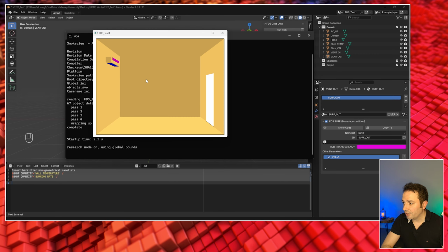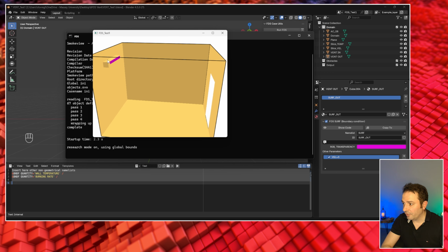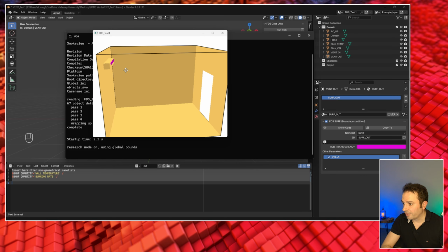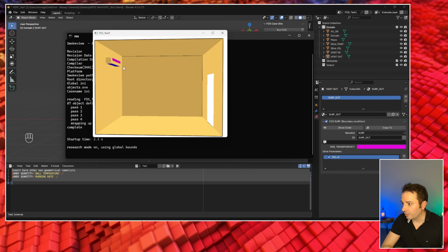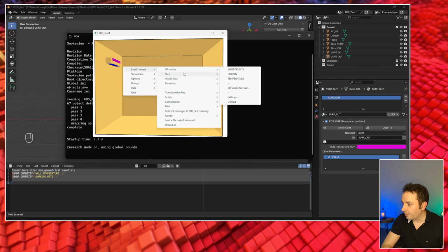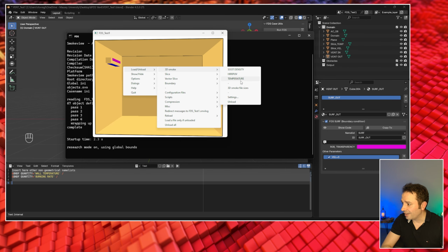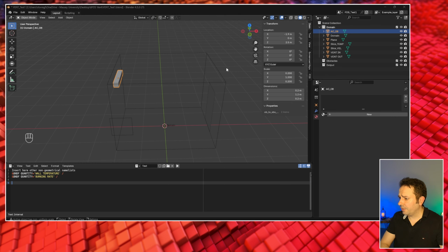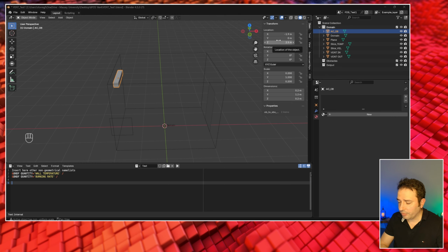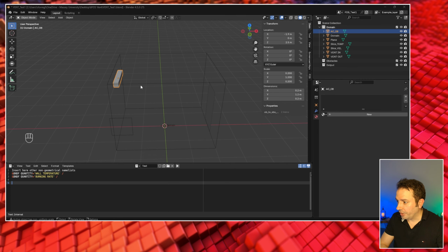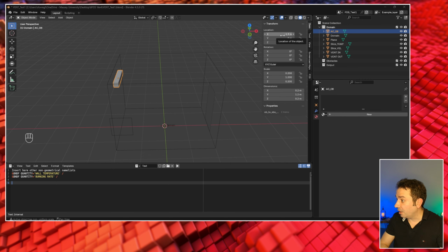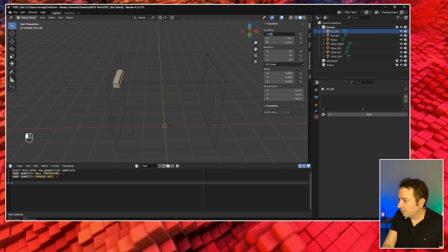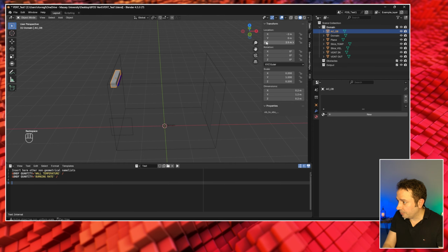So you can see that the visualization is not bad, and probably this vent has been rescaled because it's not really matching the mesh sides. So that's something that we probably need to readjust later on. But let's see if the results are affecting the domain. So I'm going to use a slice of temperature and see what's going on. So it seems that the scenario is not running as intended, and probably it's because we need to slightly shift things to make sure of the alignment between the vents and our FDS mesh domain. So I'm going to try to move things around a bit to make sure that we have a good alignment.